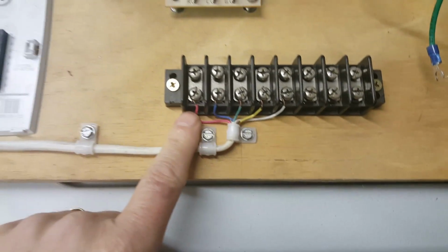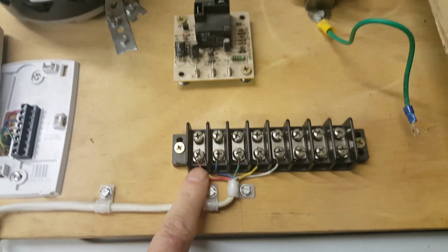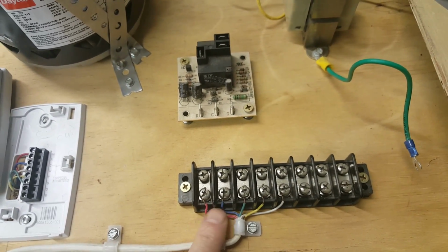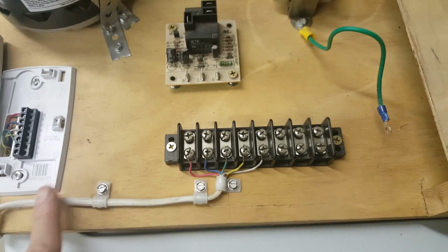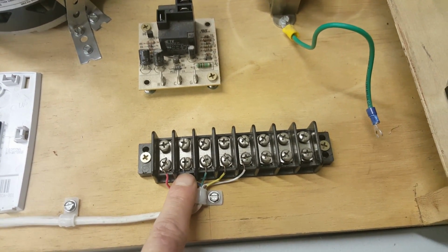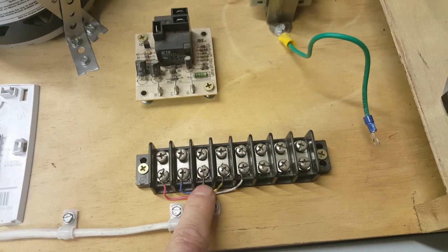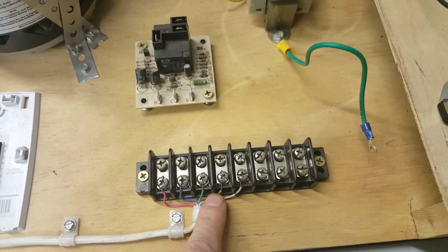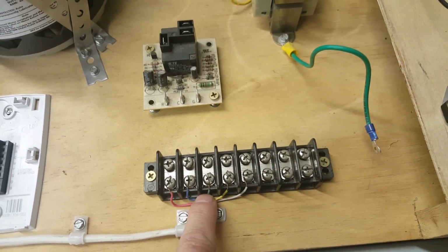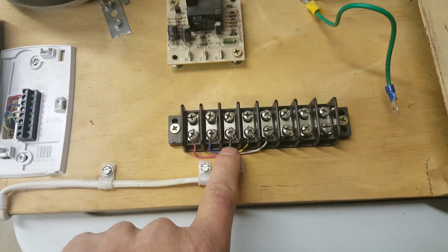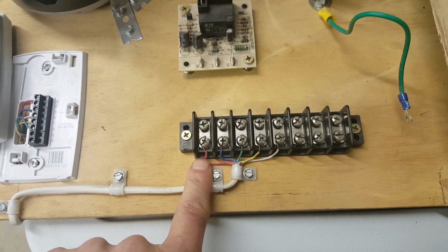So if you put your digital multimeter here across the 24 volt hot and your 24 volt common, you're going to read 24 volts. Now if you were checking to see if you're making a call for cooling on here, you would leave one leg of your meter here on the 24 volt common, and you would put the other leg here on the G to see if you had 24 volts coming back, or the Y for the cooling, because G and Y both are energized in the cooling mode. They are the same wire as the hot wire.